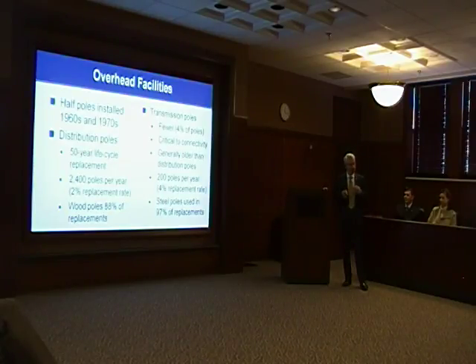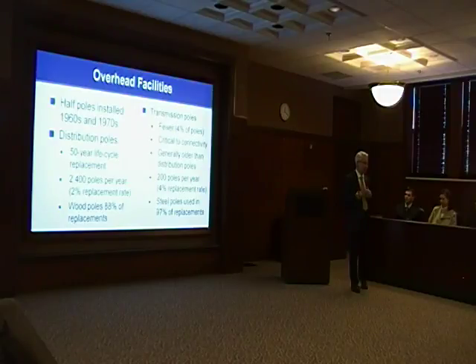On the transmission side, it's a different animal because most of that work is off the roadway, so we have to haul materials back on private easement routes a lot of times. The pole of choice there, as you see at the bottom, is steel. The typical steel pole is about 80 to 85 feet. Steel poles might cost $6,000 apiece, while a wooden pole of the same size would be about $2,000 - a $4,000 difference. That seems like a lot, but in the bigger picture of installing and moving poles around the system, there are distinct advantages to not having to pull a one-piece 85-foot wooden pole versus a steel pole that comes in sections.